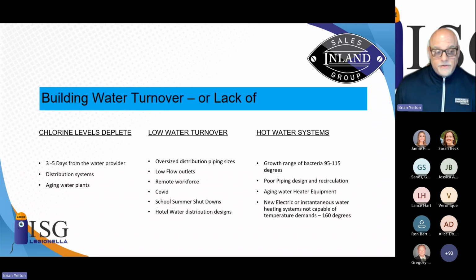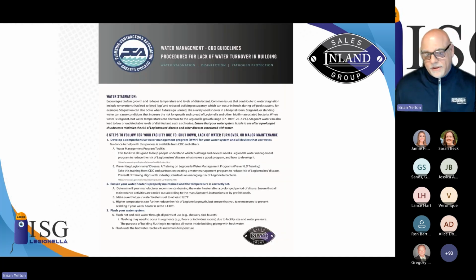So water is aging out within our buildings, and it still is today. We need to be concerned over this. These are the things we had: chlorine levels are low, low water turnover, and our hot water systems aren't working at the regulations or at the level we should be to make sure we're capable of building enough hot water and recirculating hot water. That's the key thing, getting our temperatures up and also providing protection against scalding.